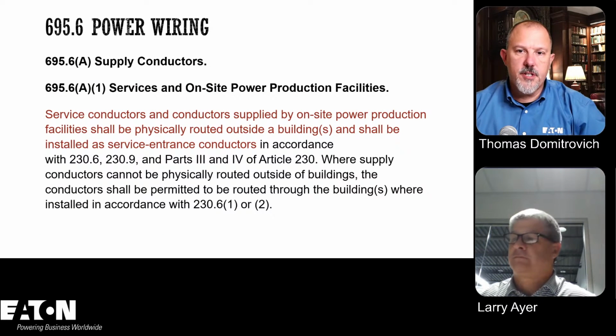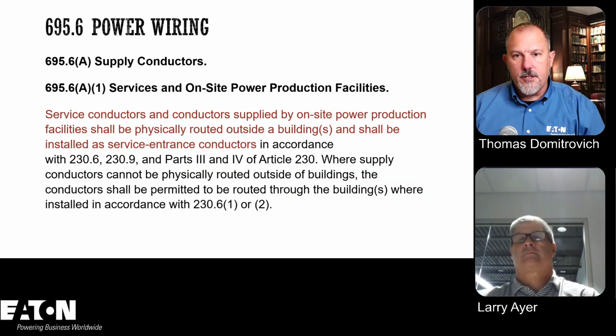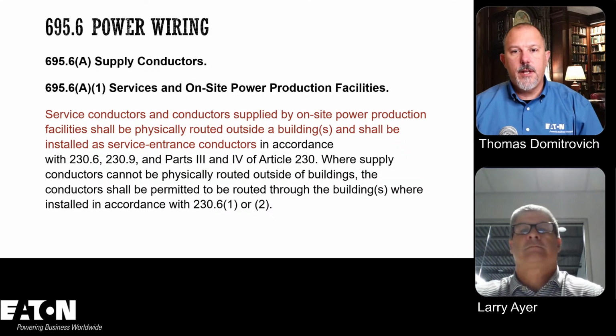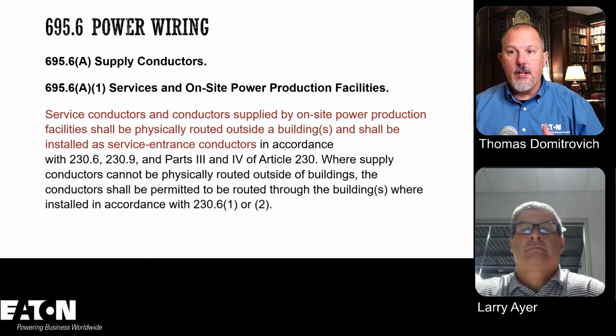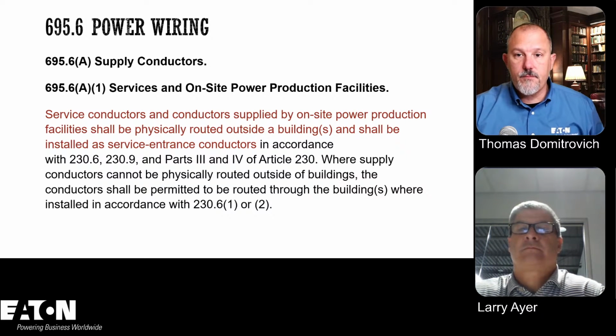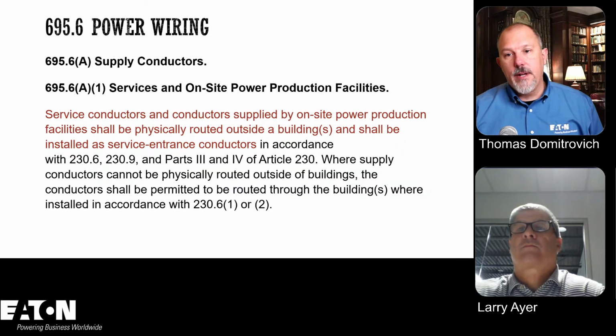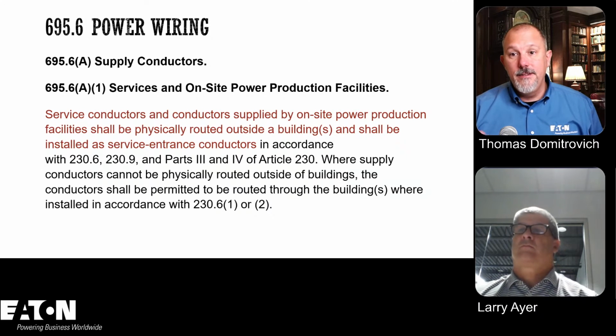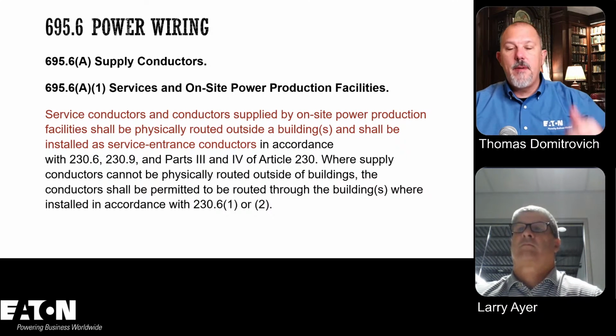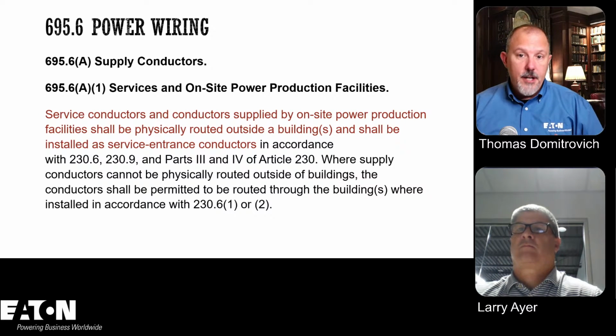Then there's your supply conductors. So now we're getting into power wiring. So these are your supply conductors, and talking about the service conductors supplying the on-site power production facilities. And this is going inside versus outside of the building. So you're still looking back at 230 for service conductors because it is a service conductor, and you're going to have to follow those same rules.